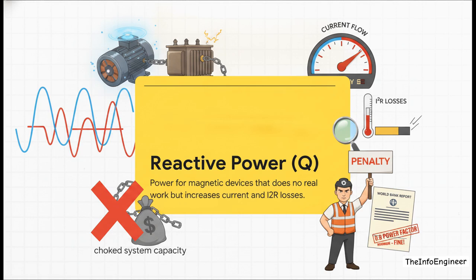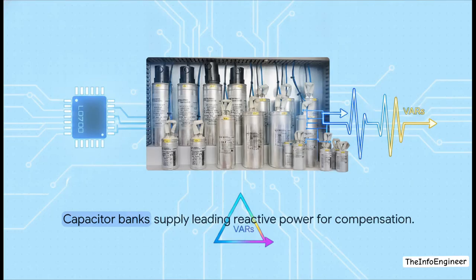Local distribution companies, your DISCOs, will slap massive financial penalties on your industrial site for any power factor that drops below their minimum threshold. So, what's the fix? Microcontroller-driven capacitor banks. We aren't talking about static capacitors that just sit there and can't adapt to changing loads. These automated systems monitor the phase angle in real time. The second your power factor drops, the microcontroller dynamically injects leading reactive power by switching those capacitors on, which perfectly compensates for that inductive lag on the fly.